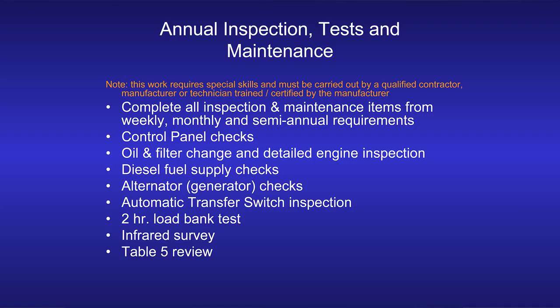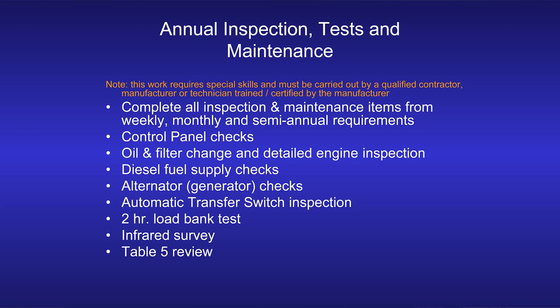Annually, you have to do, among other things, a 2-hour load bank test, done at the full load rating of the system. That exercises the engine at the maximum temperatures it's going to see, and it gives our technicians a chance to monitor the whole system through that 2-hour test to see if anything's going wrong. We also do an infrared survey while the test is going on to see if there are any hot spots due to poor electrical connections, because over time things have a way of working themselves loose, due to heating and contracting as the cables heat up and cool off when loads come on and off.